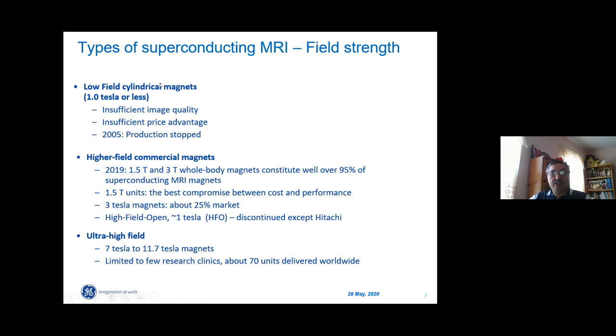This is a brief history on field strength. The first superconducting MRI generated a field of just 0.5 Tesla. Pretty soon we found that the cost of a 1.5 Tesla scanner is about the same as 0.5 and 1 Tesla. So the production of lower field superconducting scanners practically stopped. Today, 1.5 Tesla and 3 Tesla constitute well over 95% of the superconducting MRI magnets. And 1.5 Tesla is the best compromise between cost and performance.